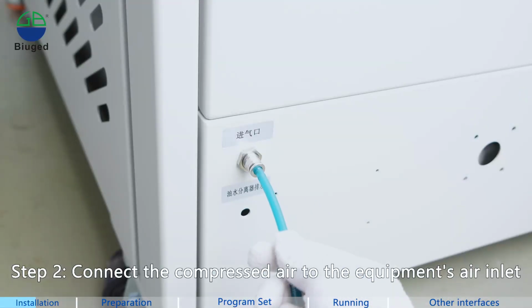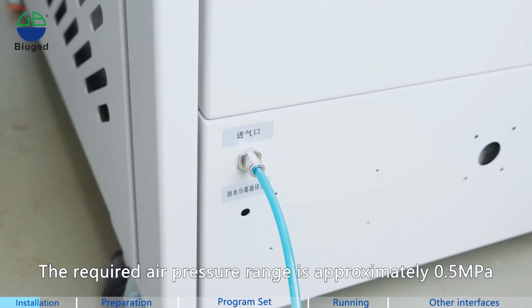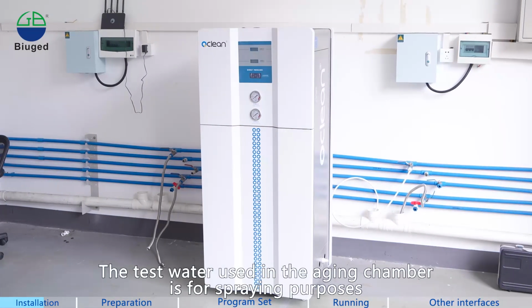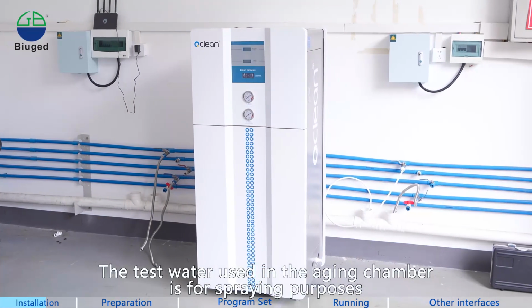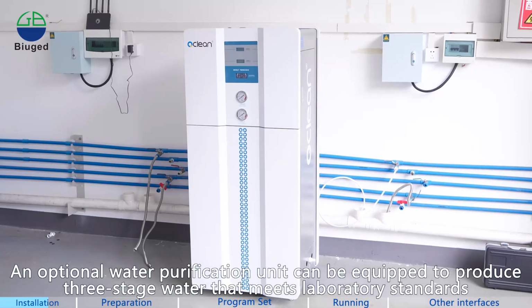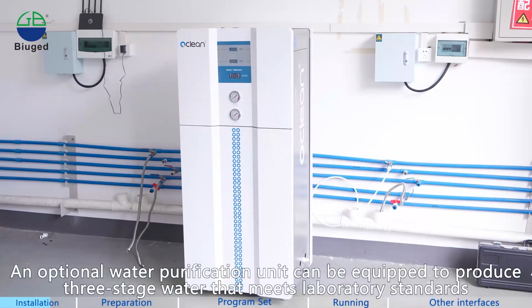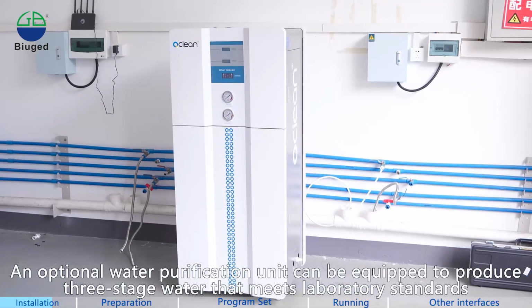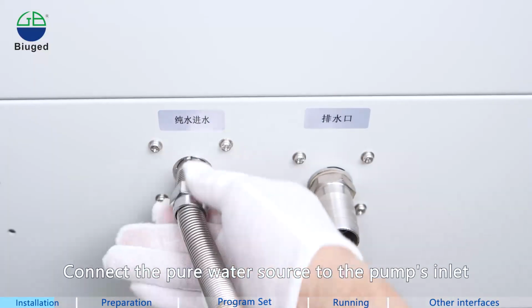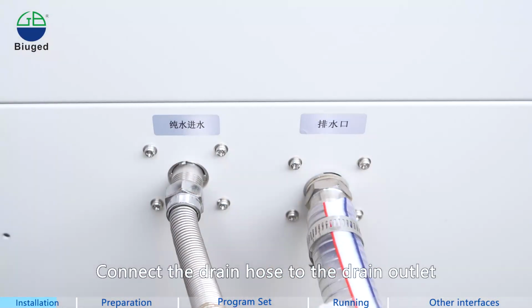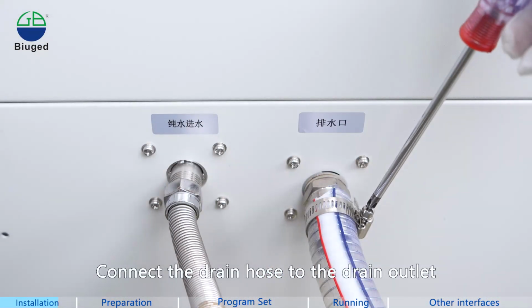Step 2. Connect the compressed air to the equipment's air inlet. The required air pressure range is approximately 0.5 MPa. The test water used in the aging chamber is for spraying purposes. An optional water purification unit can be equipped to produce 3-stage water that meets laboratory standards. Connect the pure water source to the pump's inlet. Connect the drain hose to the drain outlet.